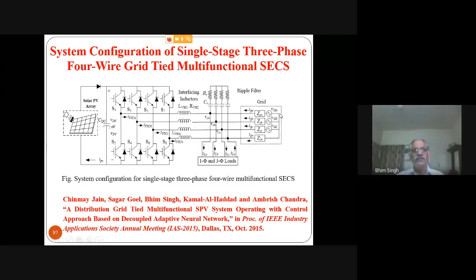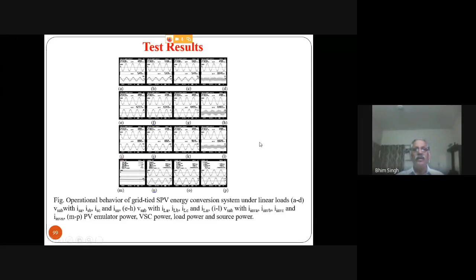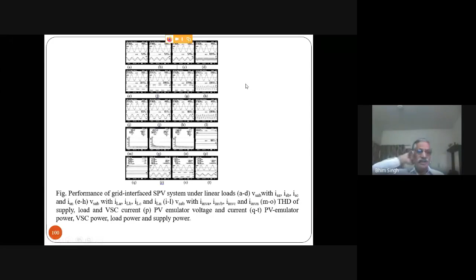You can clearly see the neutral current here is almost negligible in the three-phase supply current, because it's a balanced linear load, so you will not see much neutral current. But you can see the unbalanced non-linear load on line to neutral, because it's a 4-wire system, they are opposite but equal, and that's why the grid side neutral current is almost negligible. And it's doing all the compensation, the neutral current compensation along with the harmonic elimination, and generating the power also, all those features are already going.